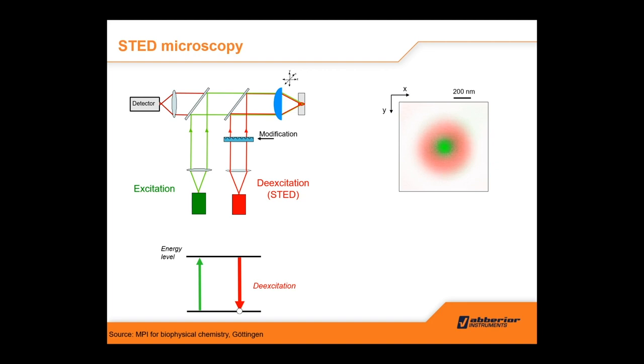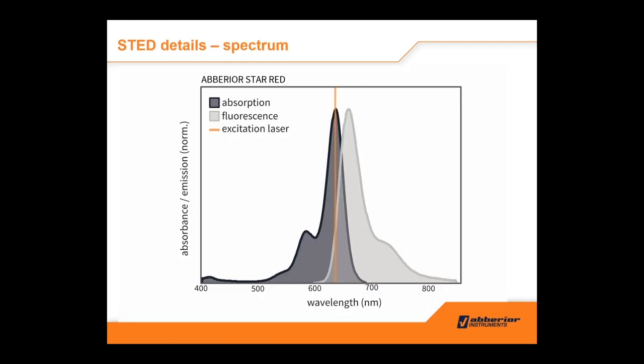If you shine the STED light onto excited molecules, it will de-excite them — bring them back to the ground state — by a process called stimulated emission, a feature found by Einstein quite some time ago. Stefan's idea was to shape this light into a donut so that everything is switched off in the vicinity of the central spot. Only the central spot remains and your resolution is much enhanced. In the spectrum of the dye, just as in confocal, you excite the dye at the excitation maximum and detect the emission. For a dye like STAR Red, you excite at 640 nm and deplete with the STED laser at 775 nm and detect in between.